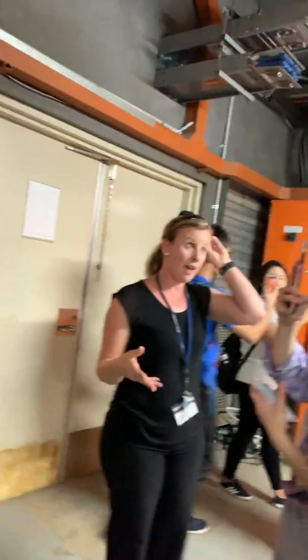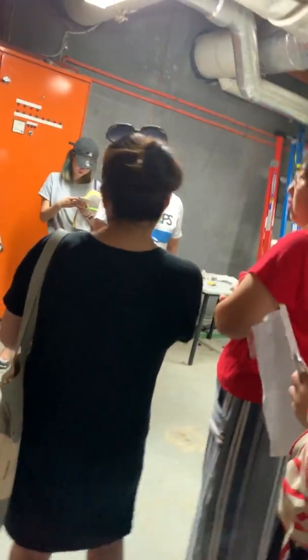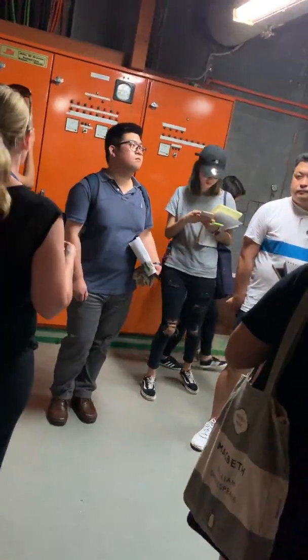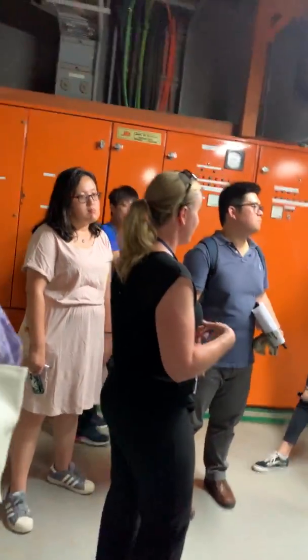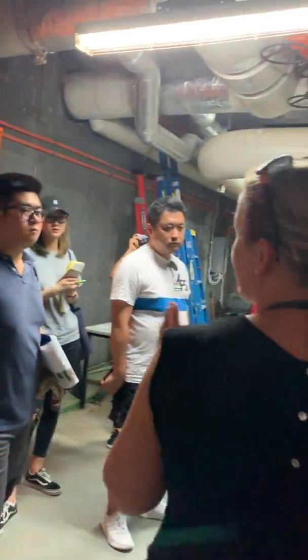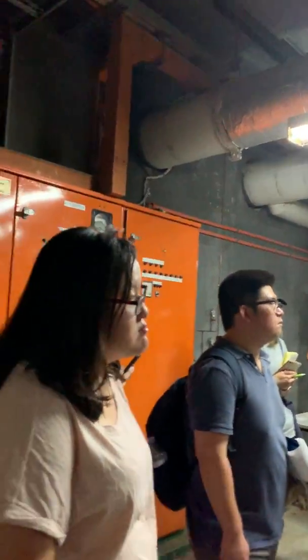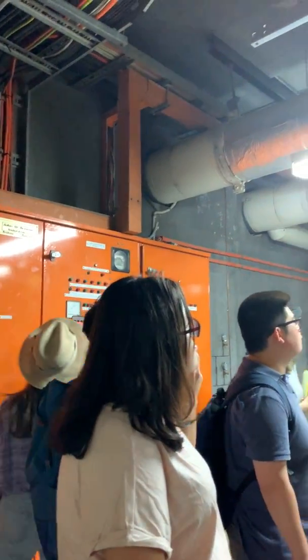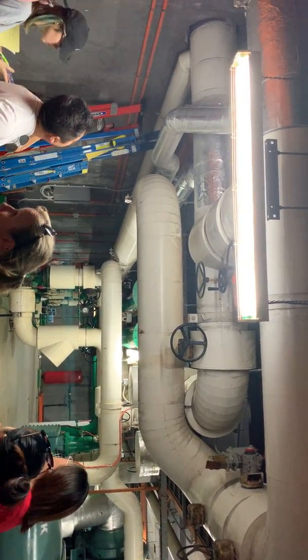So I said before that we have 2 rooms like this on campus. So what we have running around campus is a big ring loop. So we have pipe work that runs all the way around campus and just constantly circulates chilled water around. And then each building has its own pump and can draw water out of that ring loop that goes around. The white pipes that you can see, and also the silver pipes, they have the chilled water inside them. So they're insulated pipes to keep that chilled water at 5 degrees.